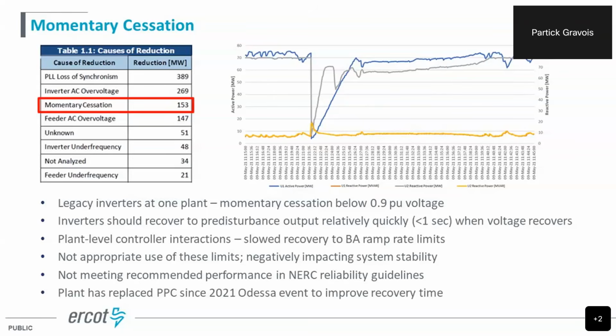So they had a lot to look at from this event, but it was clear that they weren't meeting the recommended performance from the NERC reliability guidelines. Since 2021, this plant had replaced their entire plant level controller, retuned the logic, and they were expecting to be able to come back quickly after momentary cessation, but we found that was also not the case in the 2022 event. And again, we'll come back to this facility later.